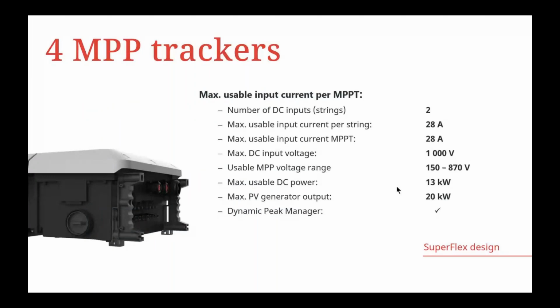When we talk about the design flexibility of the Fronius Verto, we have introduced 4 MPPTs for all the power classes that are available. Every MPPT can be connected with 2 strings of solar panels, and every MPPT current is 28 amps. Similarly, the voltage ranges are really good. It is up to 1000 volts for the DC input, and the usable MPPT range starts really low, which can help you start the inverter with only 4 to 5 solar panels, and can be extended up to 870 volts for the MPPT voltage range, and the maximum is 1000 volts.